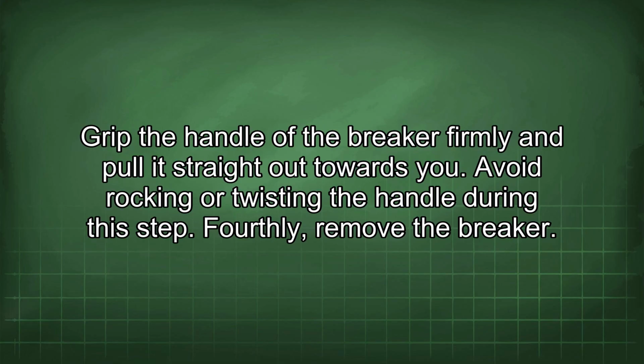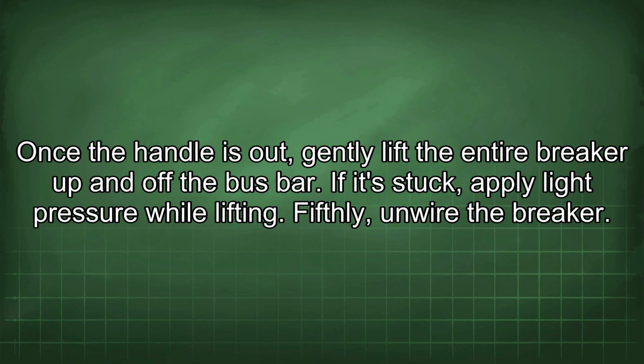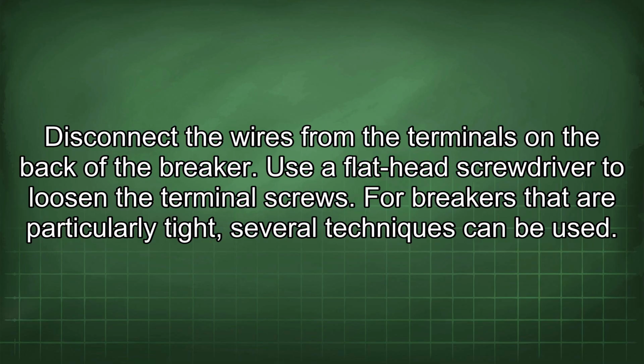Fourthly, remove the breaker. Once the handle is out, gently lift the entire breaker up and off the bus bar. If it's stuck, apply light pressure while lifting. Fifthly, unwire the breaker. Disconnect the wires from the terminals on the back of the breaker. Use a flathead screwdriver to loosen the terminal screws.